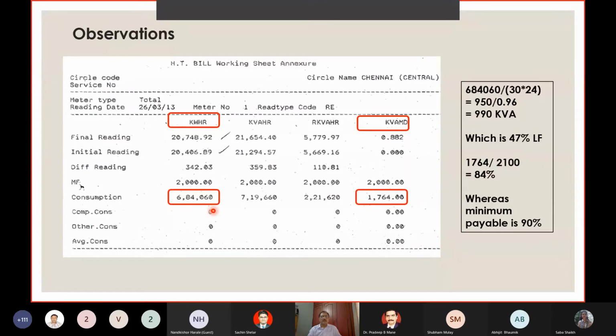The second thing, if you can notice here, 6,84,000 is the consumption for that month. Now, if you divide it by 30 into 24, this is 24 hours, 30 days, it comes to 950. And the power factor of this facility in that month was 0.96. So 950 kilowatt divided by 0.96 power factor will give you 990 kVA. This is the average demand for this consumption. But then the registered demand is 1764. So you can appreciate that there was a peak while some of the internal large machines started. The demand peak was registered, and therefore they have 1764. But in reality, if you divide this kilowatt hour by 30 into 24, you get only 990 kVA, which is only 47% of the load factor of the connected loads.